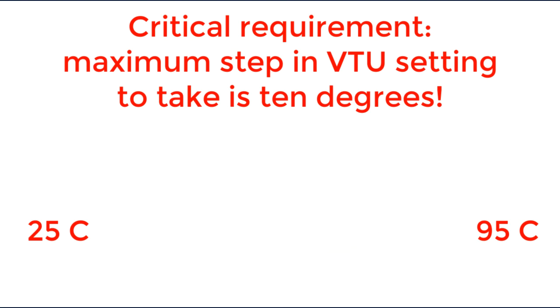It is very important that we return spectrometer back to idle state to room temperature in the same stepwise pattern at a slow pace.